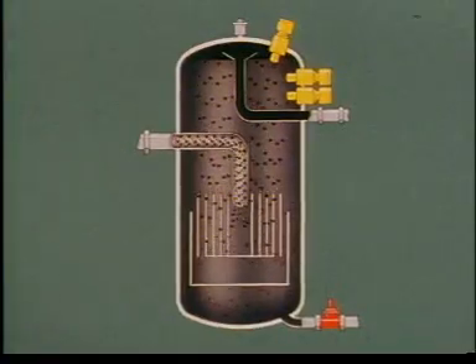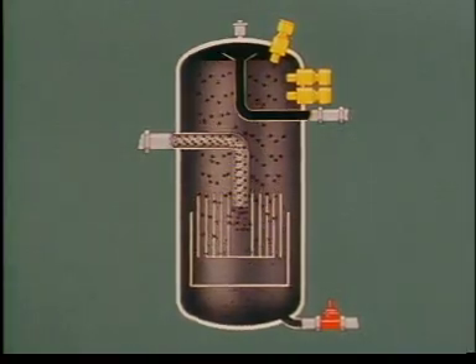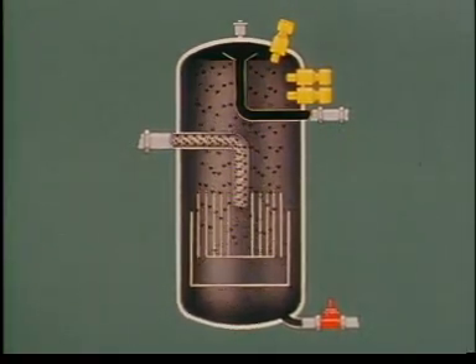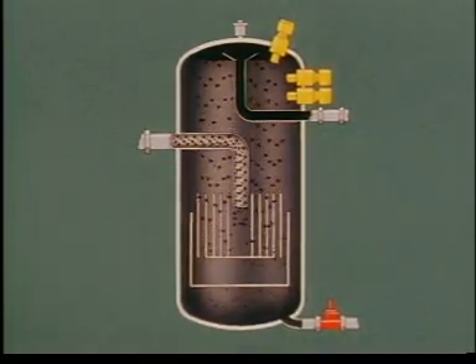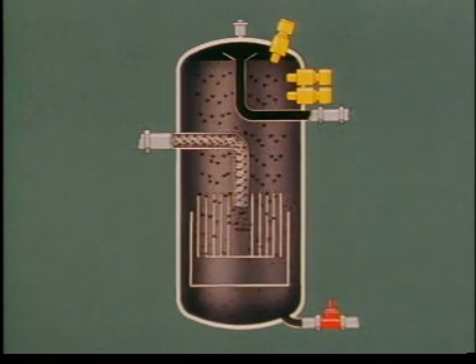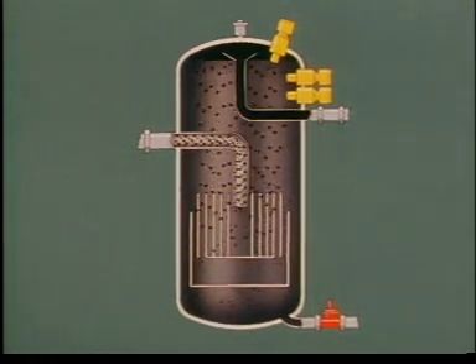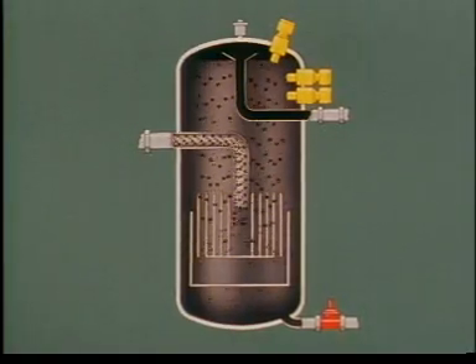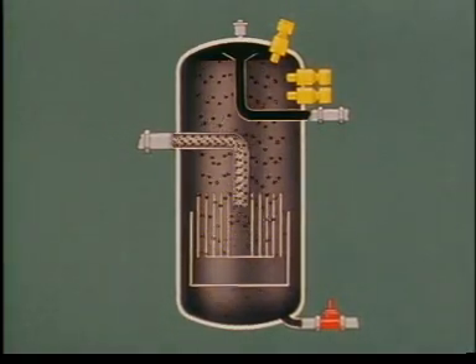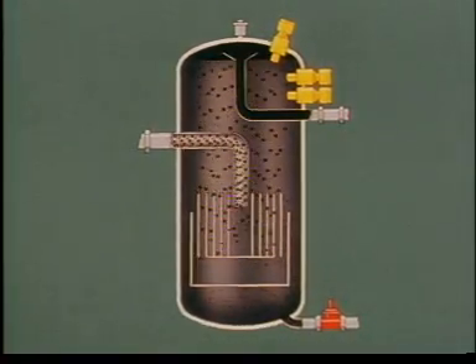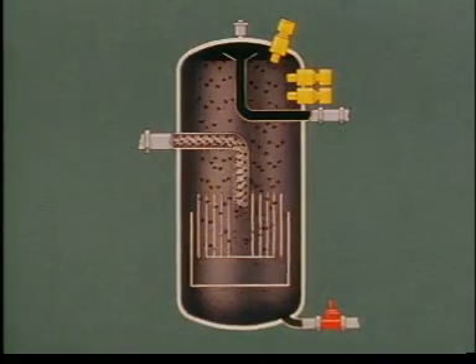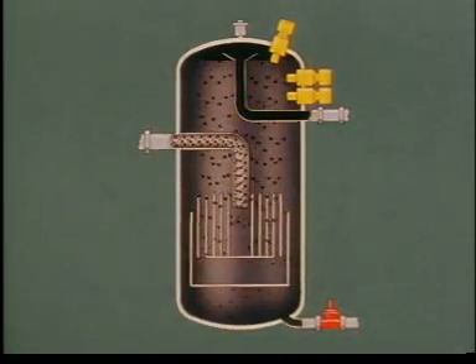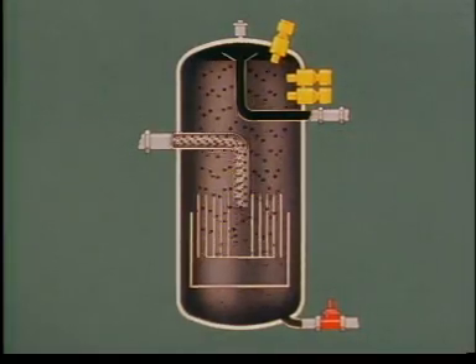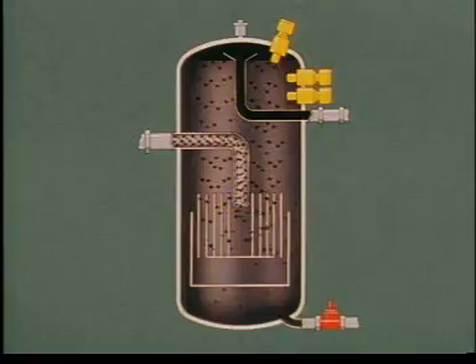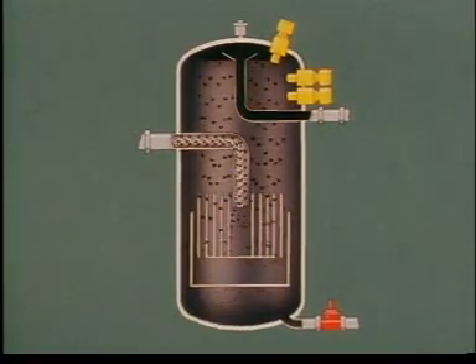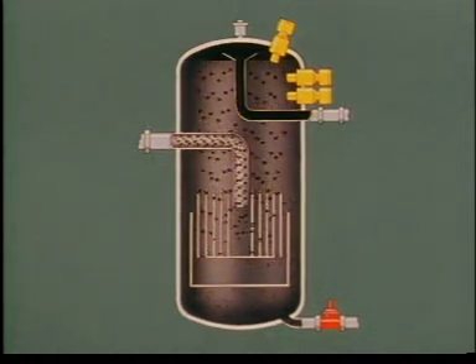The spiral ducts are surrounded by a large cylinder, open at the top and bottom. The water, with small globules, and probably a few large ones, flows down the inside of this cylinder under the base of the spiral ducts. This open cylinder is enclosed in an even larger cylinder with a sealed bottom, like a very large saucepan. The water and small globules will flow under the edges of the inner cylinder and up over the lips of the outer. By now, virtually all the large globules will have floated upwards to the top of the separator, where they collect in a pool of oil in a dome. From here, the oil is drained away to a storage tank. The water, containing now only very little oil, flows down the outside of the outer cylinder to the bottom of the separator, from which it is discharged through a pipe.